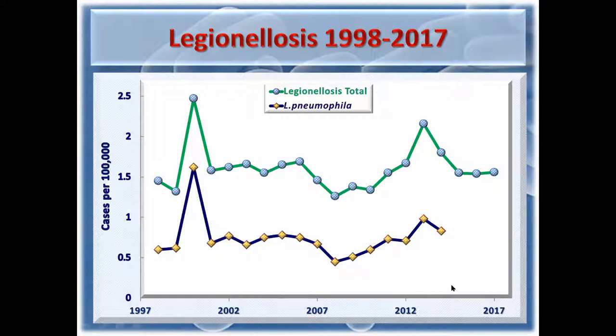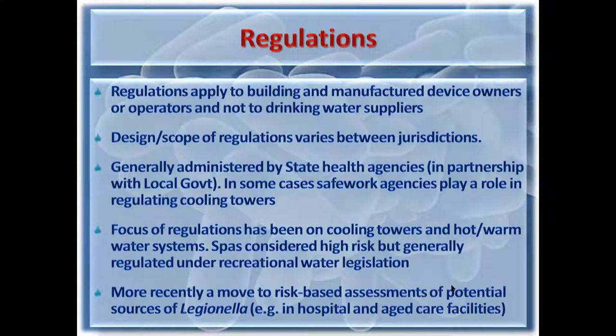Again, for context, the regulations for Legionella apply to building and manufactured device owners or operators. They don't apply to drinking water suppliers. We do not have a Legionella guideline value for our drinking water. The design and scope of regulations varies between jurisdictions. The regulations are generally administered by state health agencies in partnership with local government, but in some cases, safe work agencies play a role, particularly in regulating cooling towers, and that's not unheard of around the world.